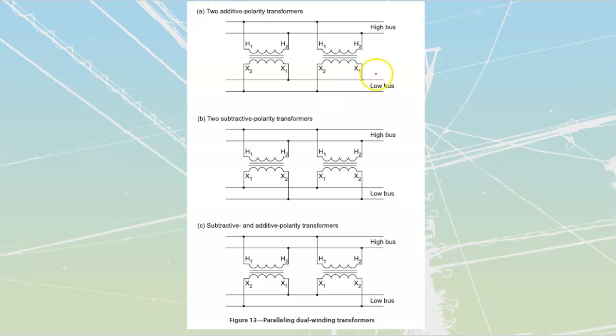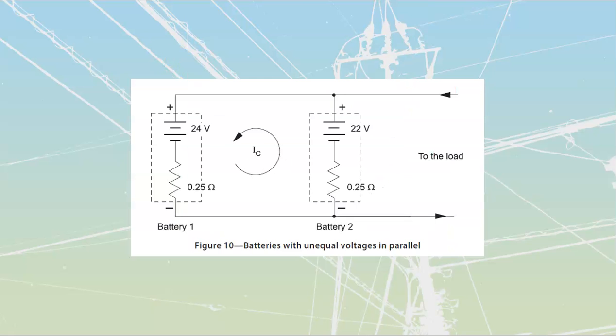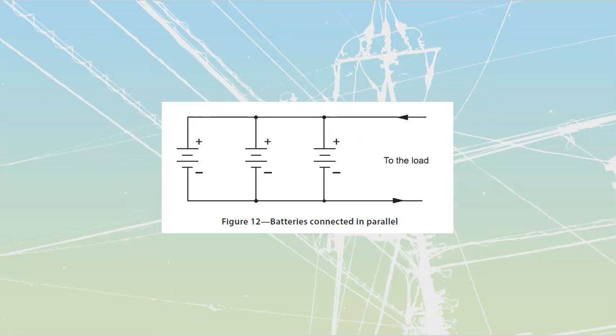In order to safely do this, we have to go back through these other steps and meet a couple of conditions. The first condition is that the transformers must have the same primary and secondary voltage ratings. This makes sense because we're paralleling together a couple of different power sources.